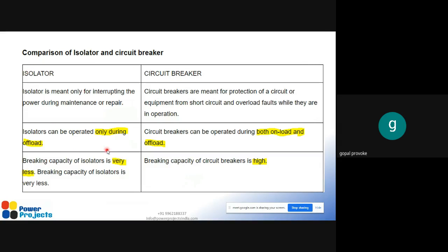So an isolator can be operated only during off-load, and circuit breakers can be operated both during on-load and off-load. The reason we operate the isolator off-load is that the breaking capacity of the isolator is very, very less, and the breaking capacity of the circuit breaker is high. So that is why the circuit breaker can be operated during on-load and off-load, but the isolator can be operated only during off-load.